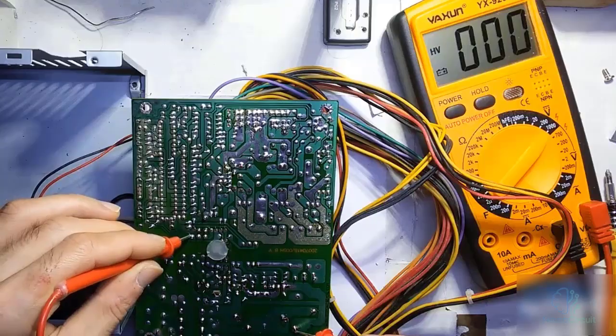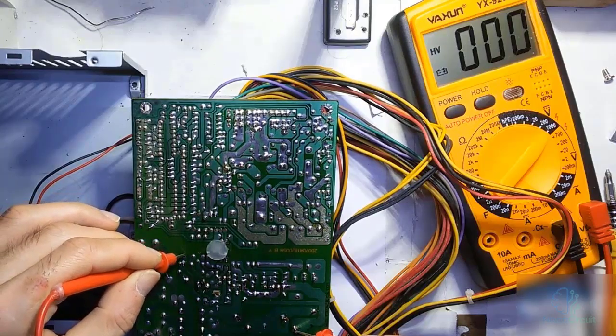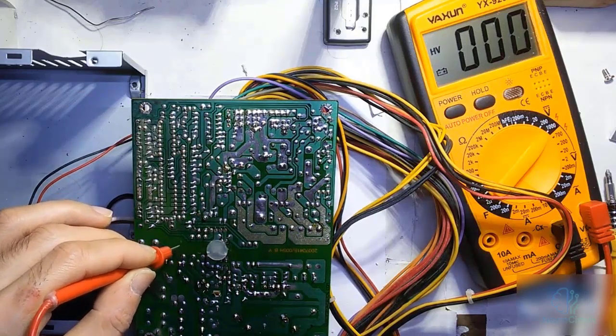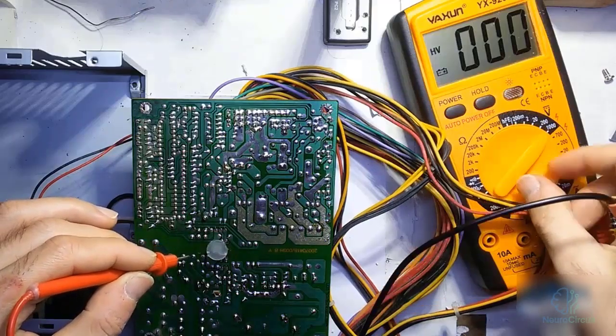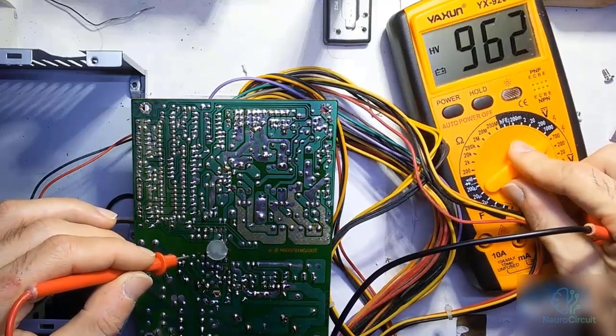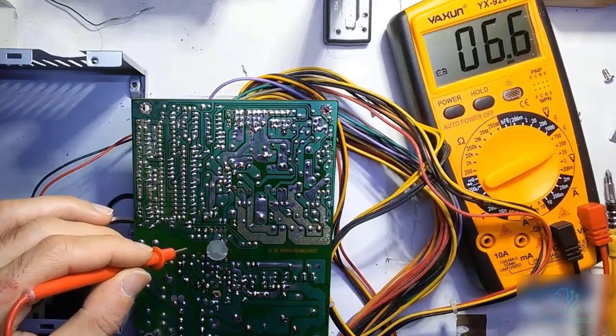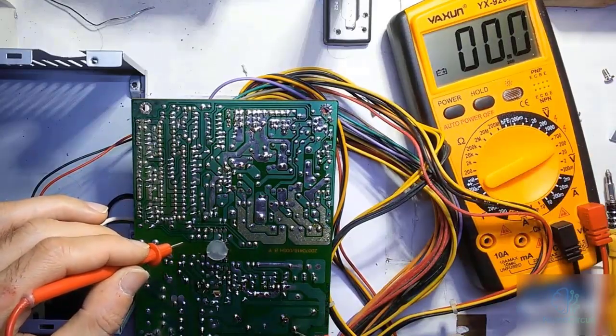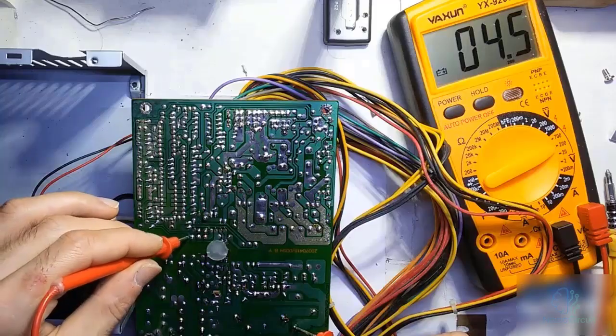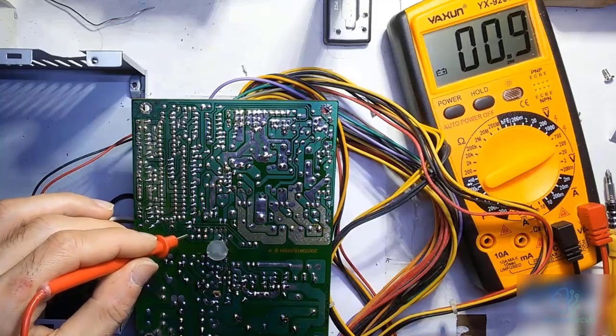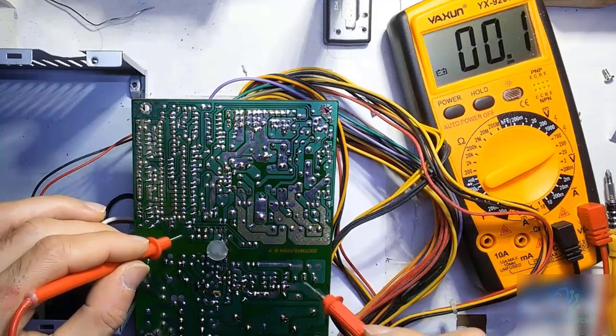Now let's measure the output voltage of the transformer to see if we have an output or not. Since transformers work with AC current, we have to set the test to AC mode on the multimeter, and test once more to ensure everything is functioning correctly. This time we're testing the output power of the transformer — we are no longer concerned with its input.